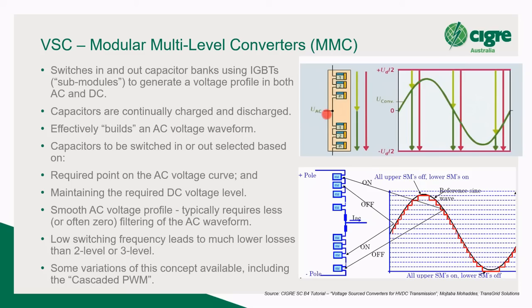So at this point, it sees a voltage of zero. Now, why doesn't it just not switch any of them in? It's because, remember what I said before, the converter also needs to build a DC voltage waveform. So here you can see the red line represents the DC voltage, which is more or less a constant voltage it's trying to build. If you can imagine a very simplified version, these capacitors are constantly charging and discharging, so they change in voltage over time.